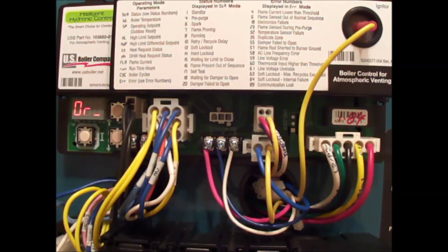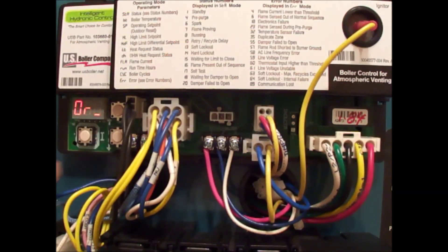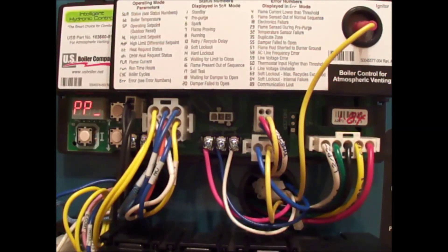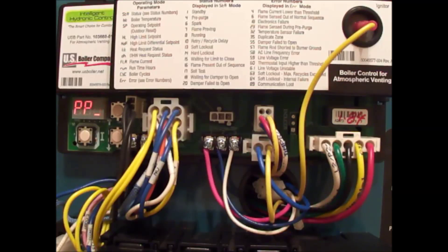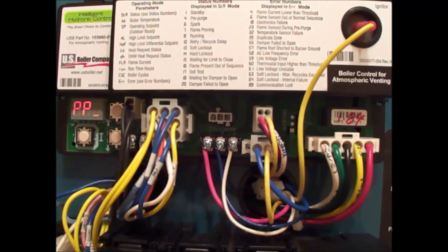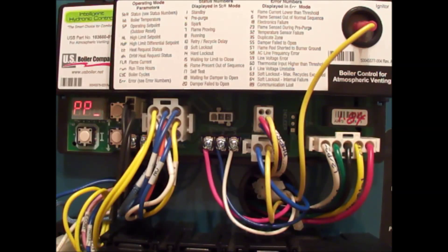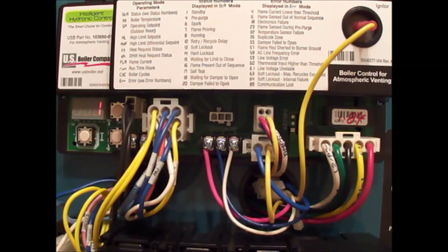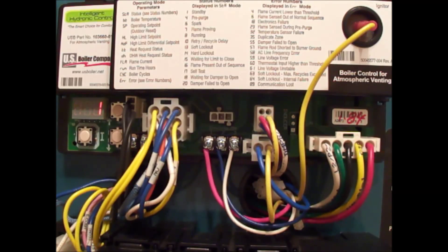The next one we have is pre-purge. Pre-purge is a setting where the pump comes on first and we use residual heat first. This is a nicer feature because we're using the heat in the boiler before we fire the boiler. If the boiler has more than 140 degrees water temperature and we get a call for heat, we do not fire the boiler.